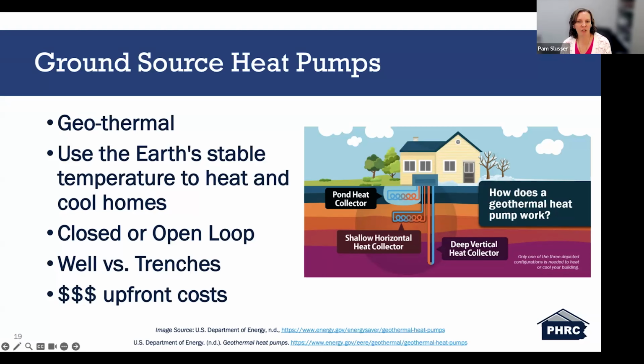And the advantage to the wells over the trenches could be you're down deeper in the soil, whereas with trenches, you're closer to the ground level. And if you have a dry summer and the ground starts to dry out, that heat could actually start to penetrate down in closer to your trenches, to your piping as well. So with these systems, there is a greater upfront cost to installation, but the data is proving that over time they do save money as they are more efficient.